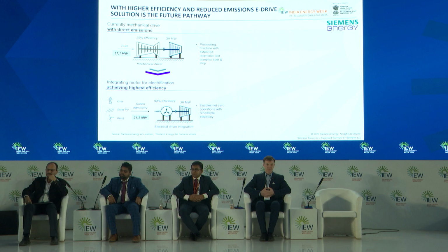So on top, you see the current situation today. To produce 20 megawatts of compression energy, you need the equivalent of about 60 megawatts of fuel, because turbine efficiencies are at about 30 to 35%. This would have been a good solution probably 20 years back when we didn't have innovative solutions enough to electrify this. Now if we look at the image below, that's the solution: converting it into electrical drives, which jumps the efficiency from 35% to about 94% for the drive itself. That means you need about 21 megawatts of equivalent energy to get about 20 megawatts of output. So that's an exponentially beneficial result.